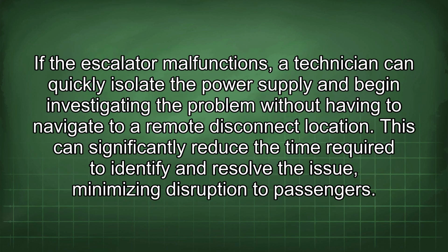Moreover, a disconnect in the pit can facilitate troubleshooting and diagnostics. If the escalator malfunctions, a technician can quickly isolate the power supply and begin investigating the problem without having to navigate to a remote disconnect location. This can significantly reduce the time required to identify and resolve the issue, minimizing disruption to passengers.